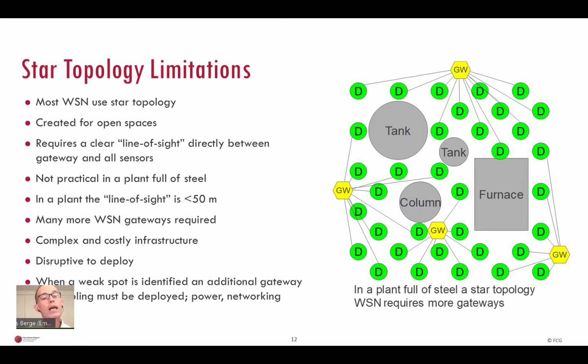Anyway, so most wireless sensor network technologies use star topology, meaning the gateway communicates directly with every sensor point to point. Because the radio waves cannot penetrate steel, star topology radio communication requires a clear line of sight between the gateway and all sensors. That is, it must be possible to see the gateway from every sensor location for it to work. For open spaces like homes and offices, on city streets and in crop fields, this works fine. Star topology can work. However, in a plant, the line of sight is limited to perhaps 50 meters or less.